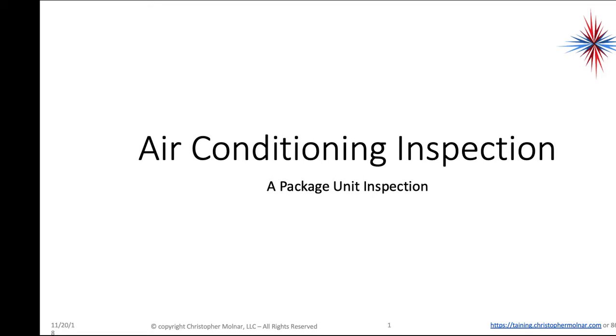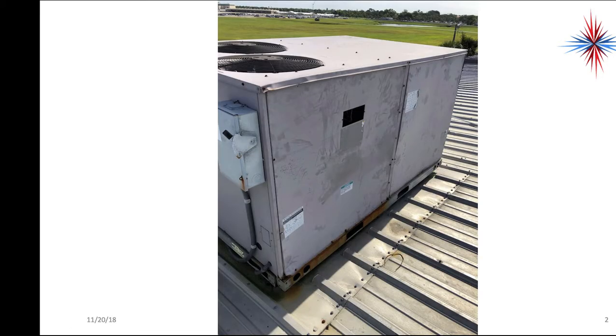In this video, we're going to be looking at an actual commercial rooftop package unit inspection. The reason for this inspection was that the customer felt that they had taken a voltage surge, a high voltage surge to the equipment, and that's why it wasn't working. Other people disagreed. So as a third party, I was called in to find out exactly what was wrong with the equipment. So we take a first look at the package unit.